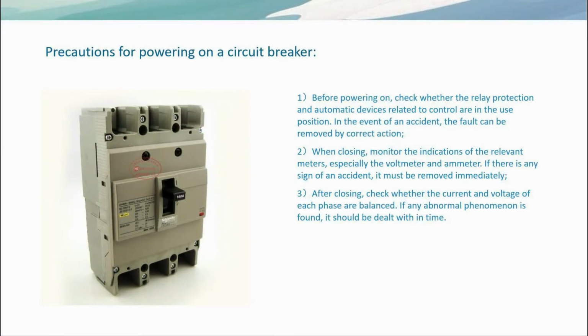Precautions for powering on the circuit breaker. 1. Before powering on, check whether the relay protection and automatic devices related to control are in the use position. In the event of an accident, the fault can be removed by correct action. 2. When closing, monitor the indications of the relevant meters, especially the voltmeter and ammeter. If there is any sign of an accident, it must be removed immediately. 3. After closing, check whether the current and voltage of each phase are balanced. If any abnormal phenomenon is found, it should be dealt with in time.